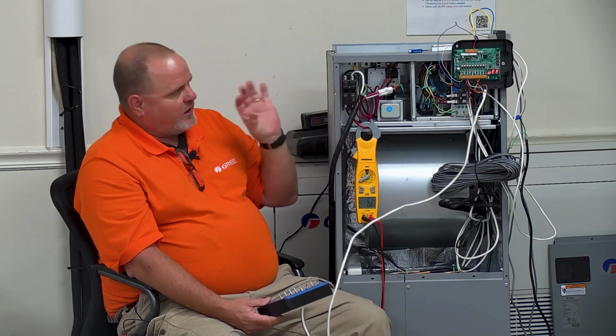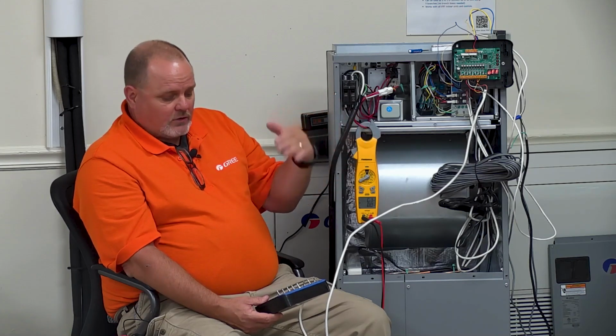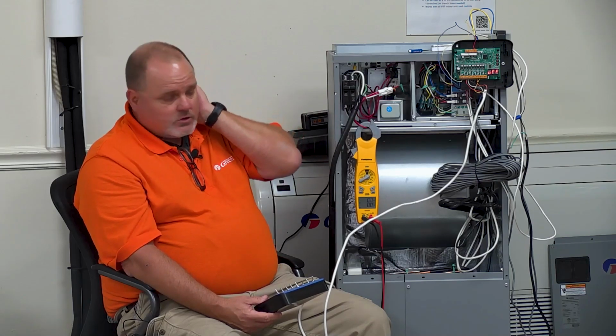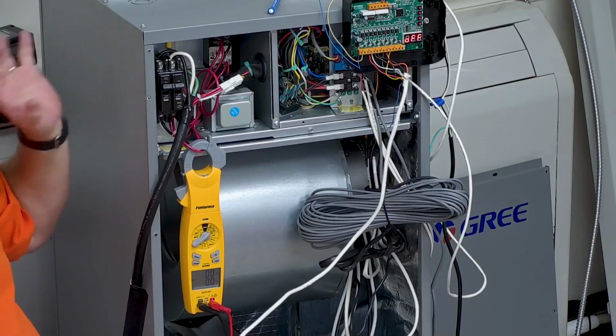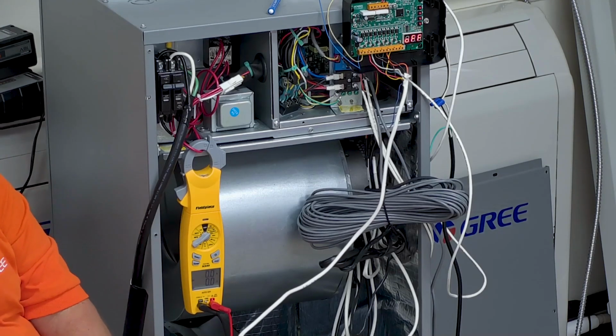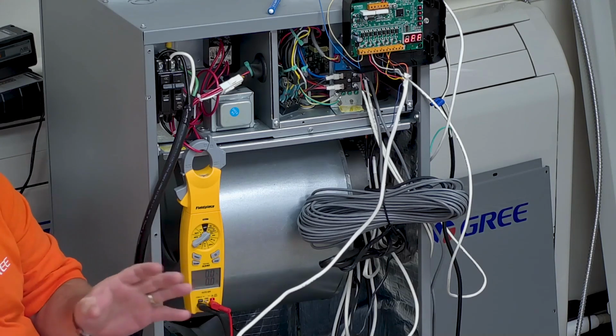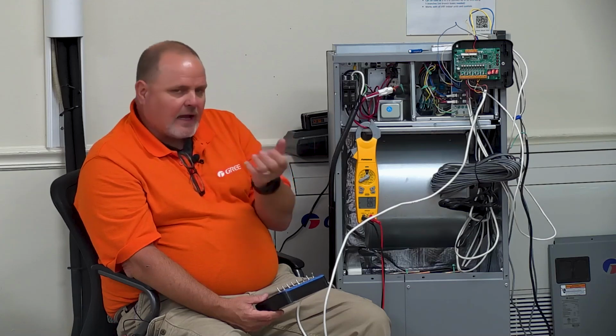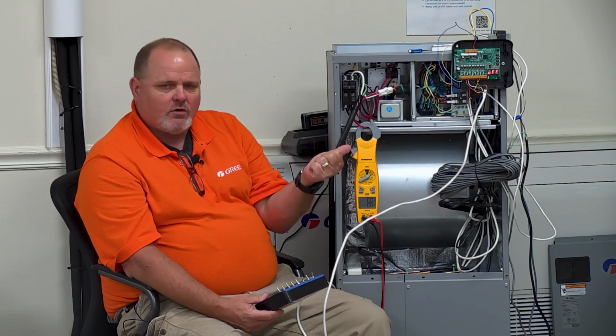Again, I really can't run it in heat pump heating mode long enough to get that auxiliary heat call, but it will function as giving you, like if you got the heat pump running and your thermostat would give you an auxiliary heat call, it will bring on the electric heat as well. So you got full electric heat control with this new 24-volt adapter. The wiring is simple because it's very similar to any unitary product you ever done with an OB terminal and a heat pump thermostat. So that was kind of the idea here, is to make it simpler for you guys out in the field and also give that homeowner the ability to use whatever thermostat they want to use.